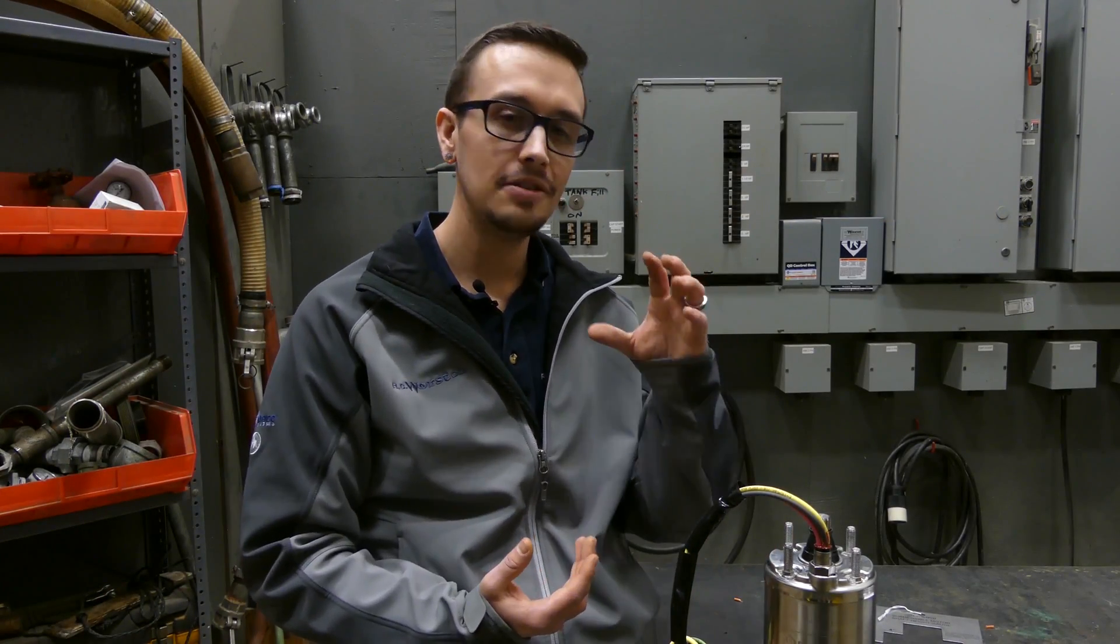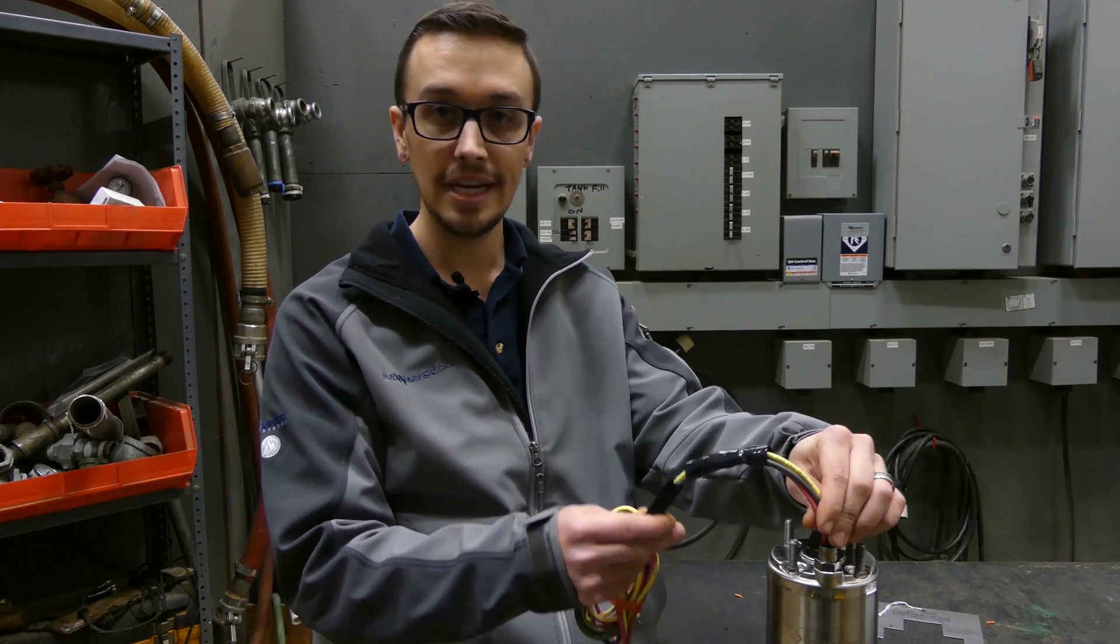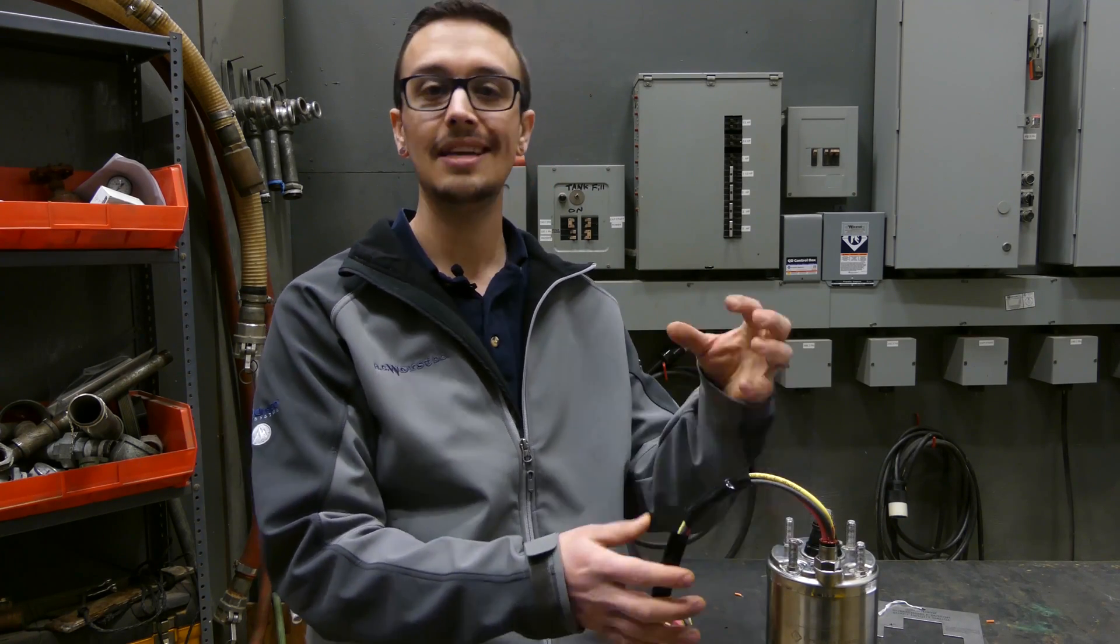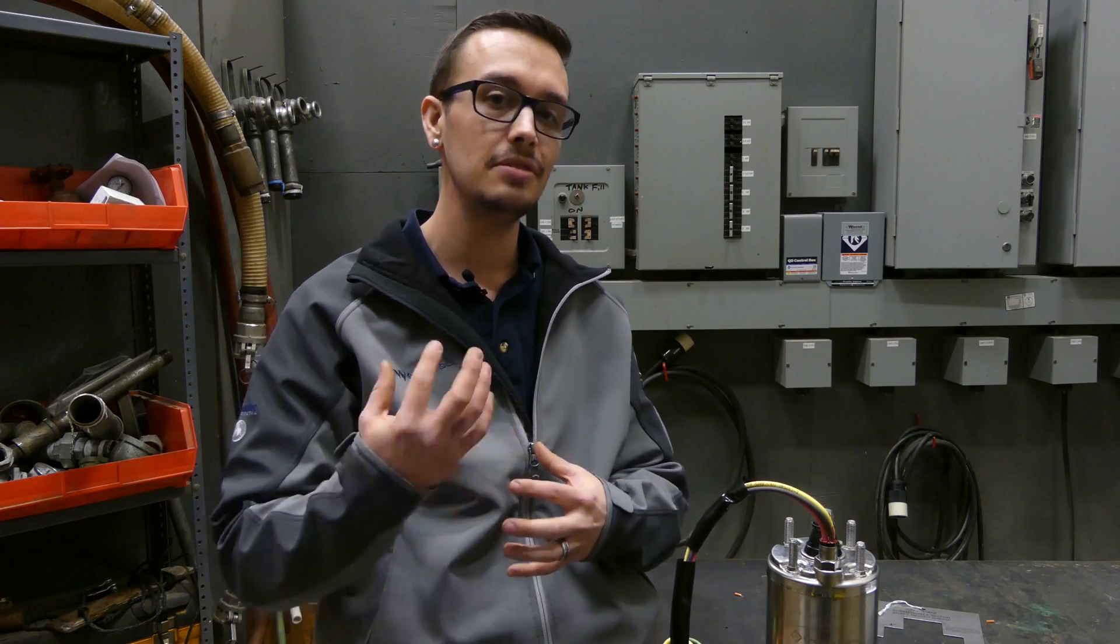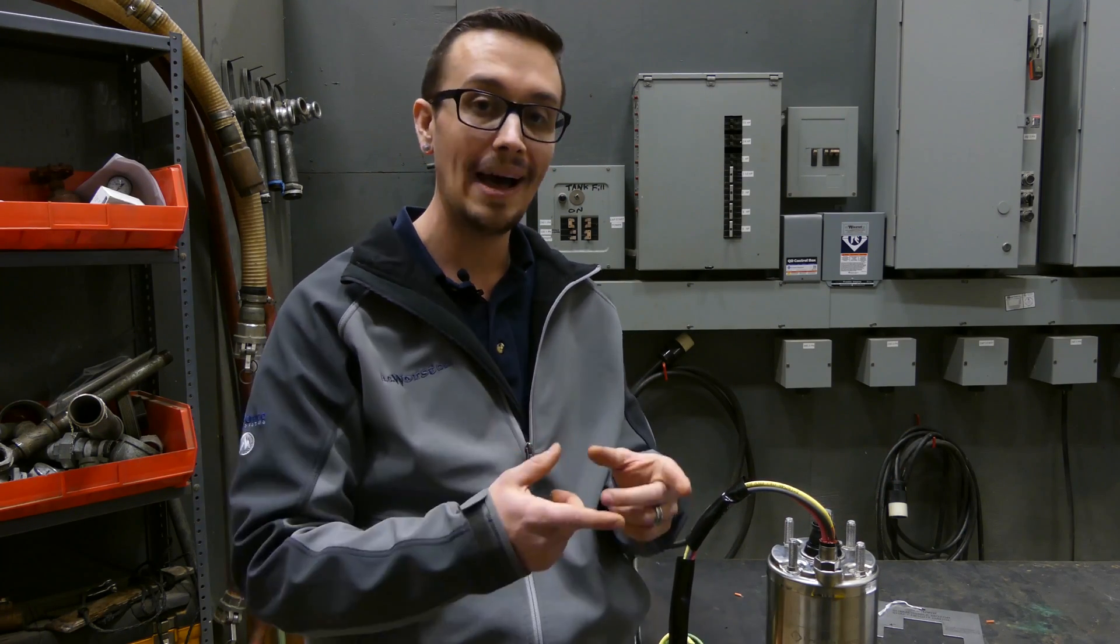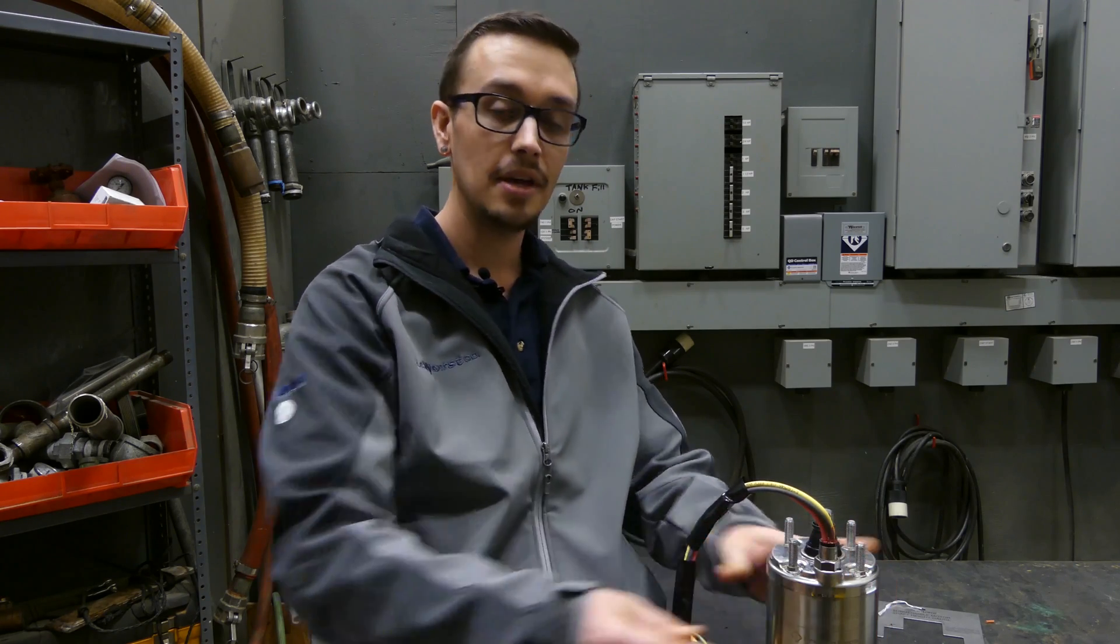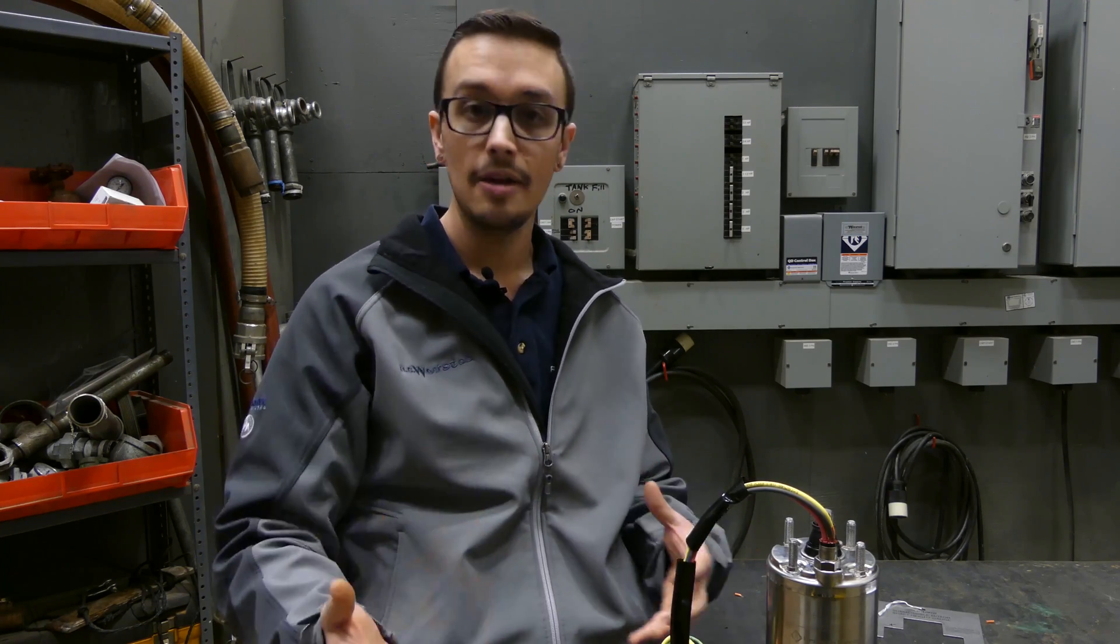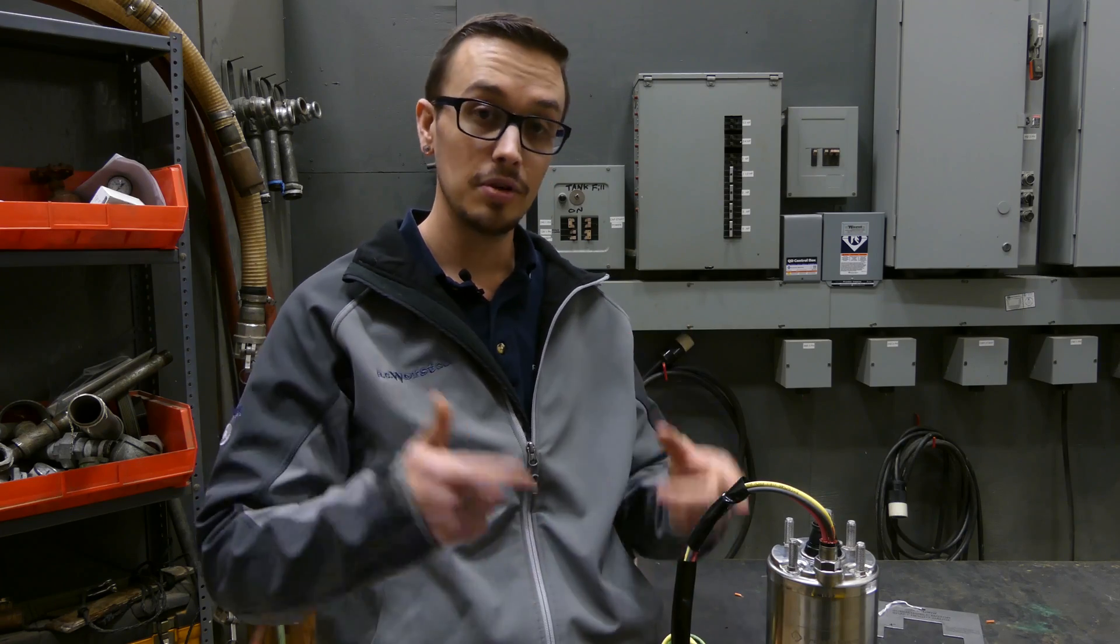The last thing that I want to remind you of: when you buy a motor or get a motor that has the lead already installed, or in the instance that you install the lead and then set the motor aside for any period of time, basically if you're not installing it right away, go back and double check that you've got 15 to 20 pounds on that nut. Because it can loosen with time, or if it was installed at the factory, maybe they didn't torque it down properly. It's better to be safe than sorry when you're dealing with a submersible well pump.